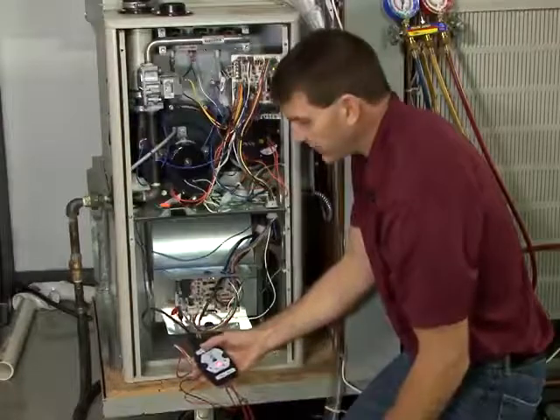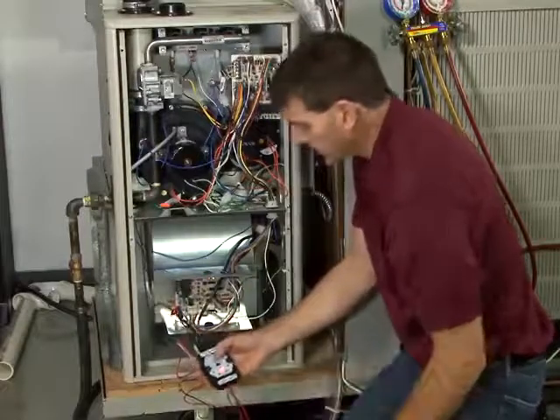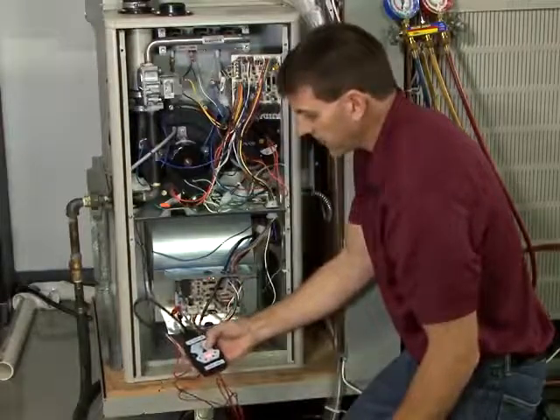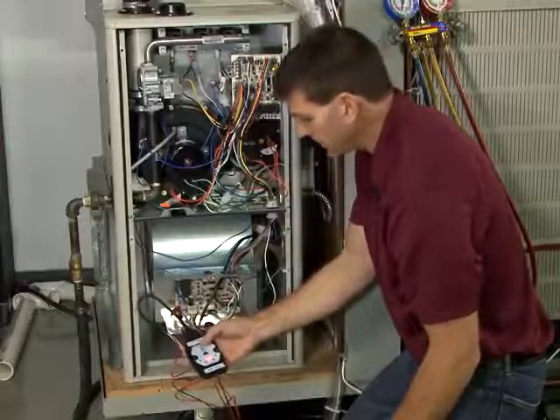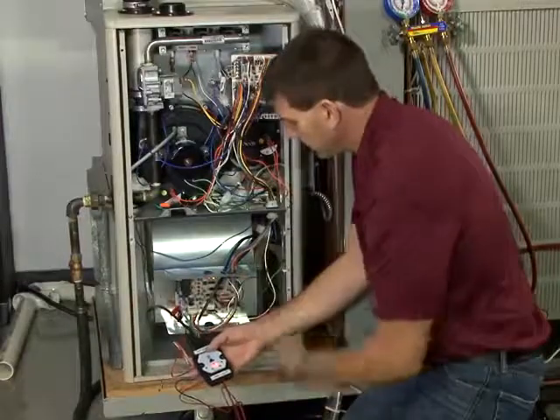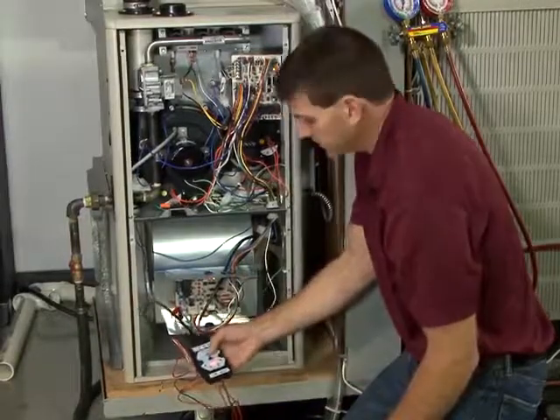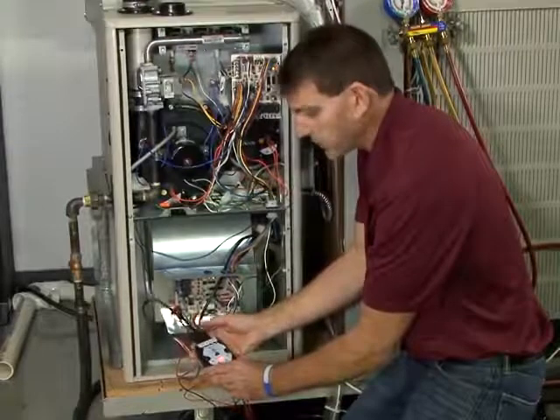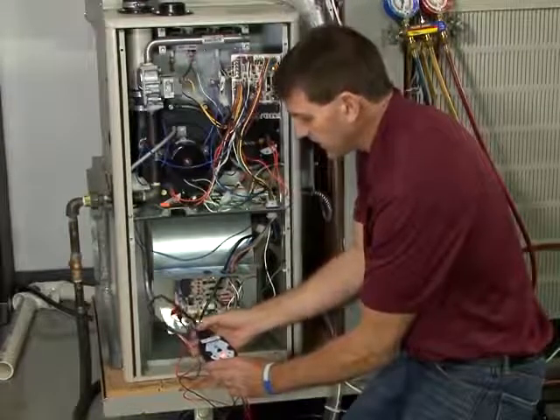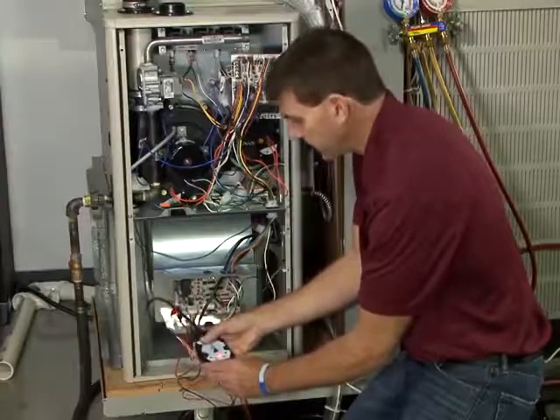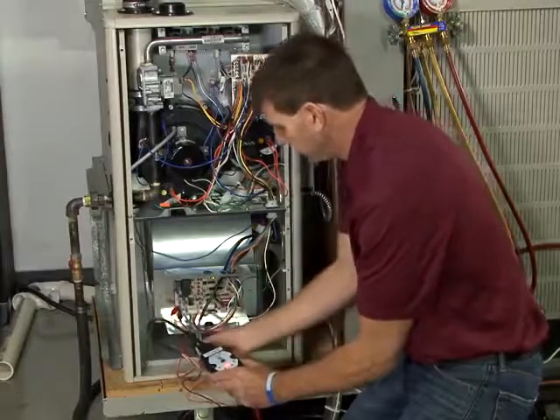If I was getting a motor fault on either one of these two boards, and I tested and proved the motor would come on with my tester, that tells me the motor board is bad. If I was getting a motor fault, and I could not run my motor with my broad ocean motor tester, then that would indeed prove that the motor is bad, and I'd have to replace the motor.